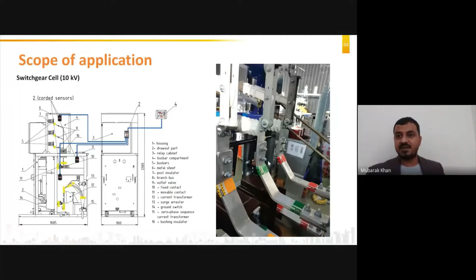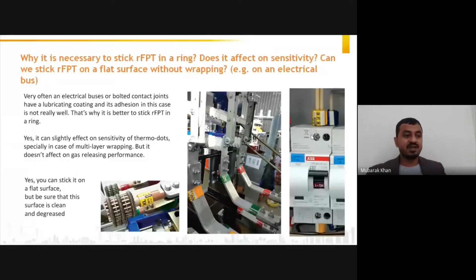Now, normally how we install the RFPT: we wrap it around the conductor, busbar, cable, etc. In a small cable, it can be wrapped like this. In a busbar, it can be wrapped like this. In a circuit breaker jaw connection, it should be wrapped like this. It is wrapped so that it doesn't fall down. Otherwise, it can work in any orientation. Moreover, while wrapping, we prefer that the thermo indication dots are at a visible angle, so that if the temperature increases, you can see the dots changing color.